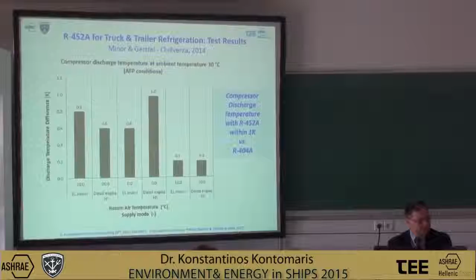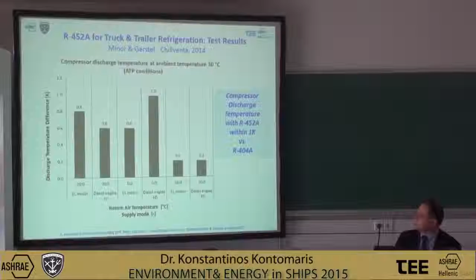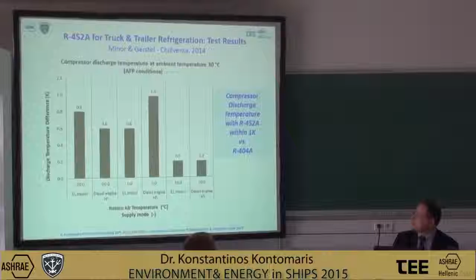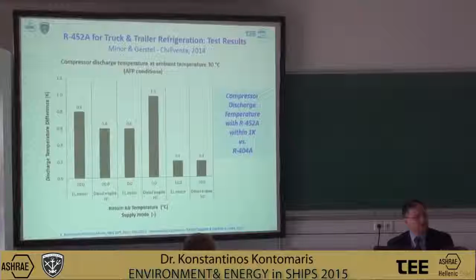Specifically for transportation refrigeration, a key requirement is that under fluctuating and often high ambient temperatures, the discharge temperature must remain within the specifications of the compressor. So there is a limit to the maximum discharge temperature that the compressor can accept. So there has been a study by a major provider of refrigerated truck and trailers, Thermo King, for this new fluid, the 452A, under a wide range of conditions, temperatures and speeds of operation of the compressor and so on, that has confirmed that the discharge temperature with the new fluid also remains very close, within 1 degree of the discharge temperature with the current fluid, the 404A.